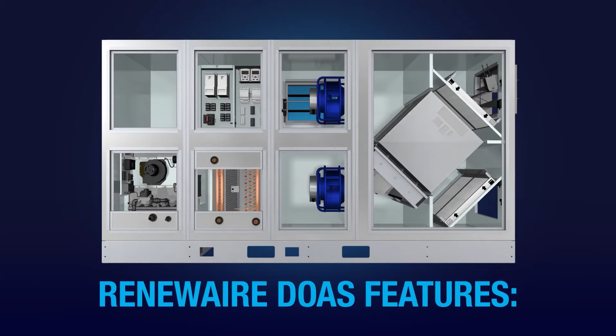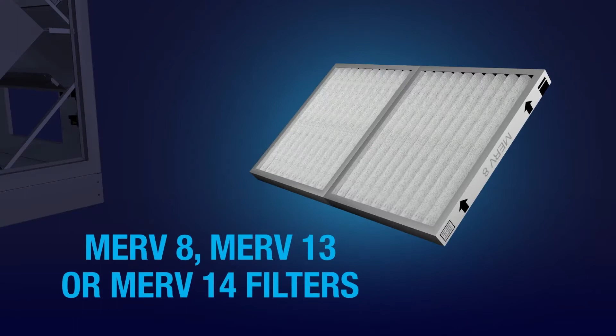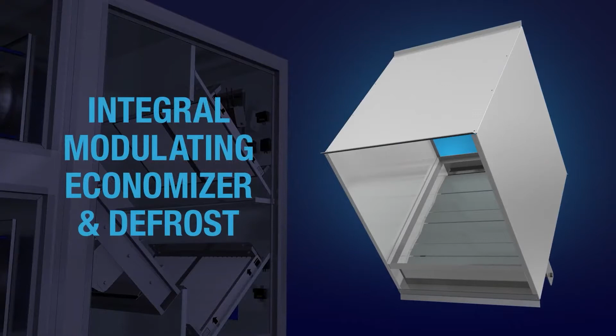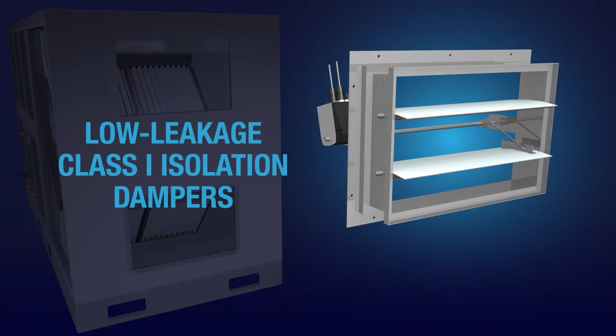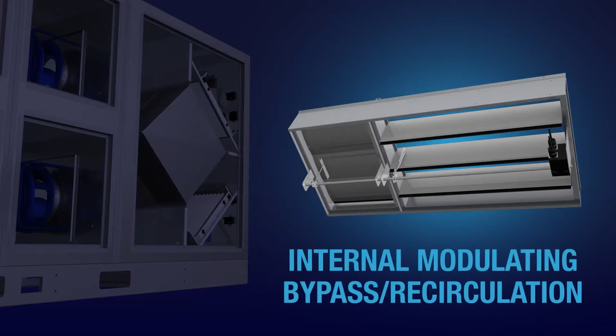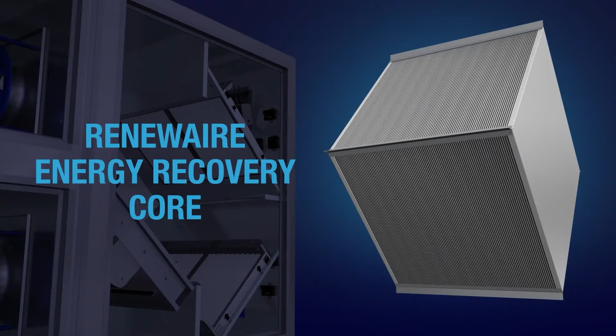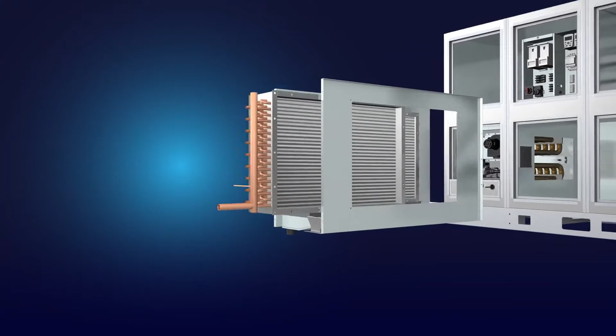We've come a long way. If you think about early engineering designs, as recently as 15-20 years ago, we were designing constant volume systems or overhead VAV systems that were basically anywhere between 15 and 20% outdoor air. There was really no importance placed on how we were delivering that outdoor air into the space, or whether we were actually providing enough. We were designing systems where at peak operation we were putting anywhere between 15 to 20%—a nominal number that didn't necessarily correspond to what was going on indoors. And there was no real thought given to how that air was being delivered to the unit from a temperature and humidity perspective. So a lot of challenges there.